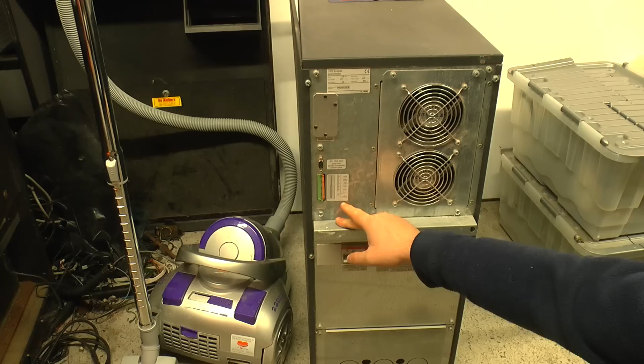Manual, which I've printed out. We've got provision for an SNMP management card, so you can plug it into the network. RS-232 communication, various connections showing whether it's mains failure or various alarms, low battery, or whether it's on load, or it's also a connection if it's running on generator. And there's a remote shutdown connection as well, which I assume is this link wire here. Take that out, off it'll go. Batteries are connected through these fuses.